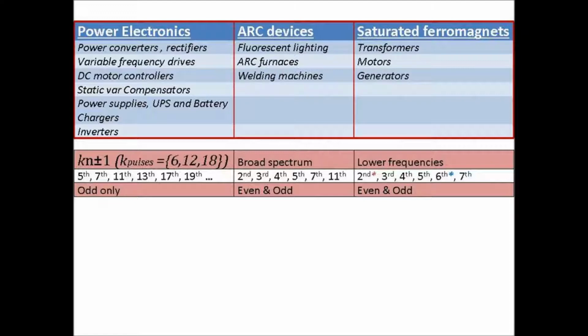I suppose in Ireland we don't have too many arc devices on the system. We did in the past. We used to have Irish Steel there, but arc furnaces are particularly bad for harmonics. They spew out harmonics across the spectrum. Welding machines, fluorescent lighting, anything with an electronic ballast, they're all under the arc devices. But the big one today, and the one that has brought the problem back to the fore, is power electronics.